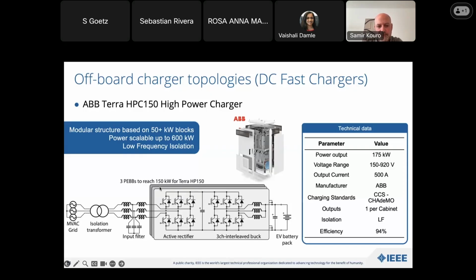It uses 3 PEBBs, each one of 50 kilowatts, to reach a total of 150 kilowatts. It looks like a back-to-back configuration, but in fact one stage is used as AC-DC while the other is used as DC-DC, operating not as an inverter but as a DC-DC converter, working as a 3-channel interleaved buck converter.